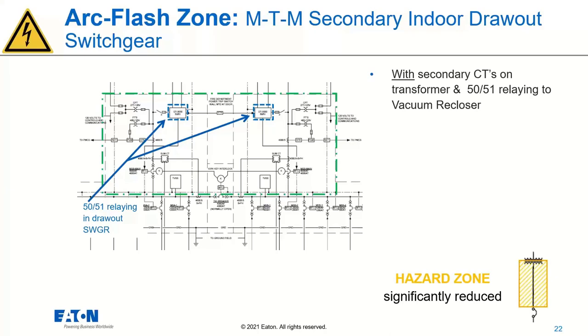So as we add in those secondary CTs, we don't have to rely on that inrush. We don't have to coordinate with that inrush. We don't have any inrush because we're downstream of that core coil. So we can set the protection settings on the 50/51 much, much tighter than we could if we were doing something with a primary set of CTs or a primary device.